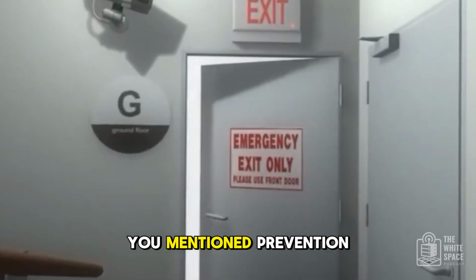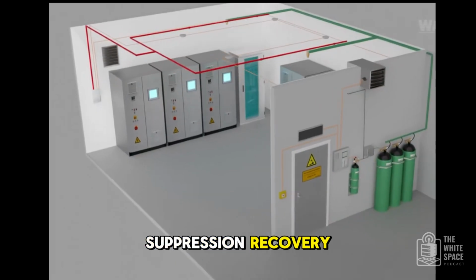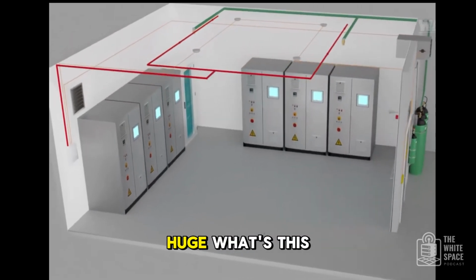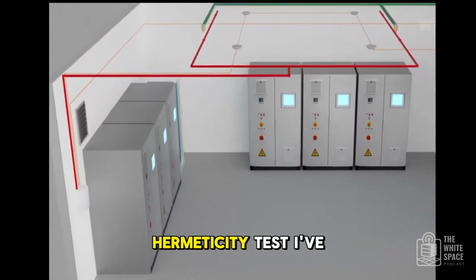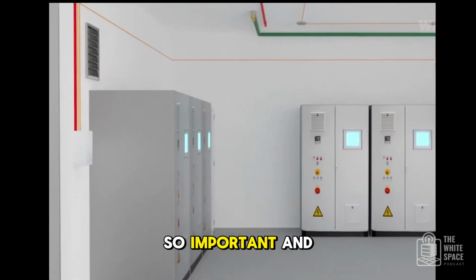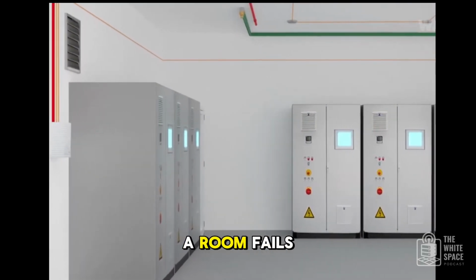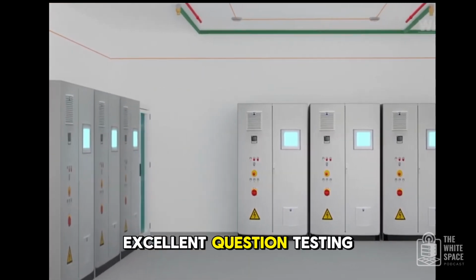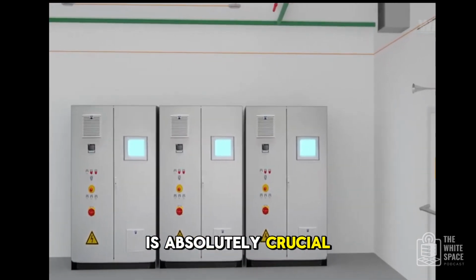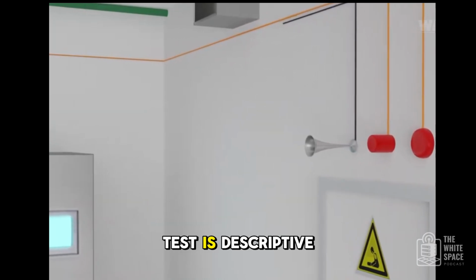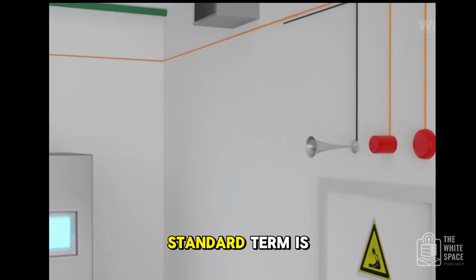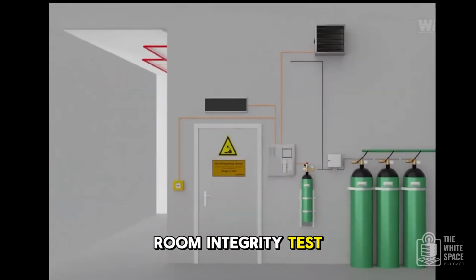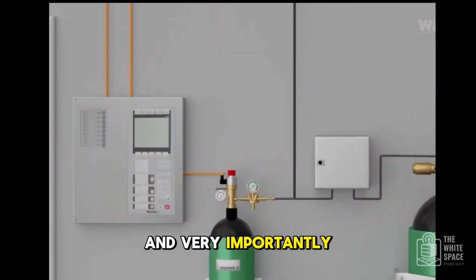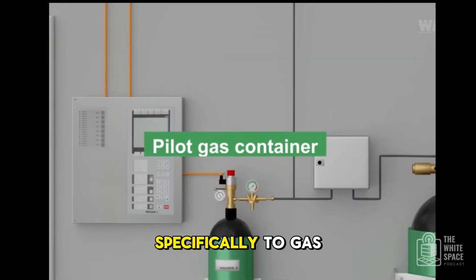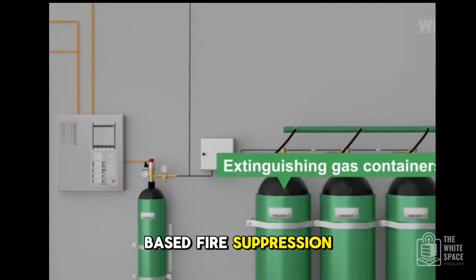What about testing? You mentioned prevention, detection, suppression, recovery. Testing must be huge. What's this hermeticity test I've heard about? Why is that so important? And what happens if a room fails it? Excellent question. Testing is absolutely crucial. That term hermeticity test is descriptive, but the industry standard term is room integrity test, or RIT. And very importantly, this test applies specifically to gas-based fire suppression systems.